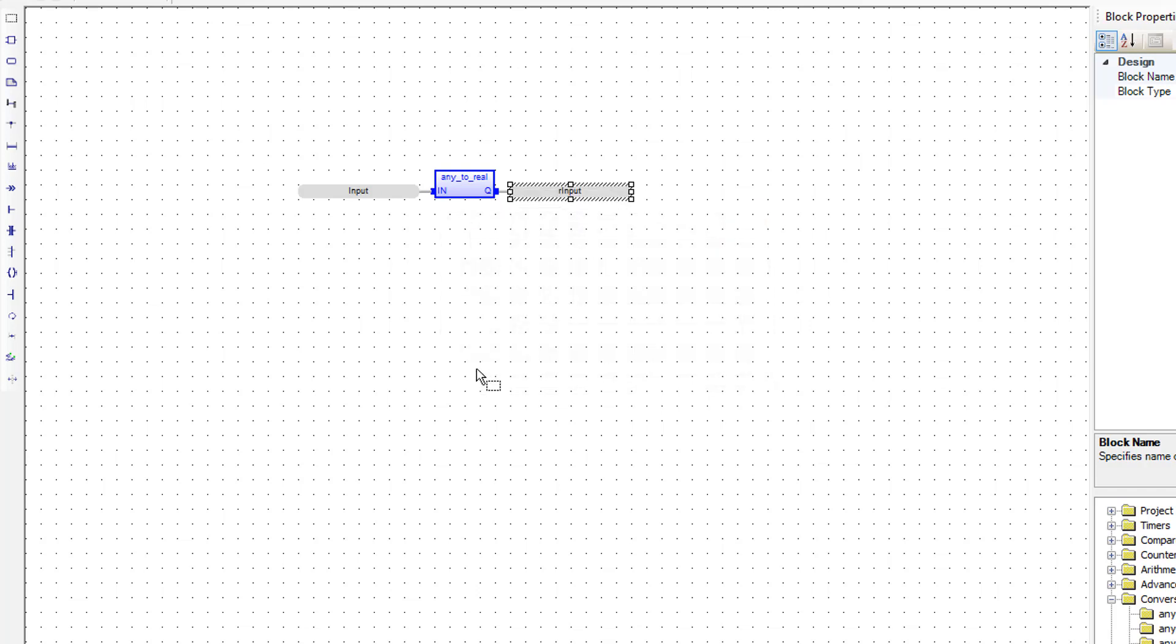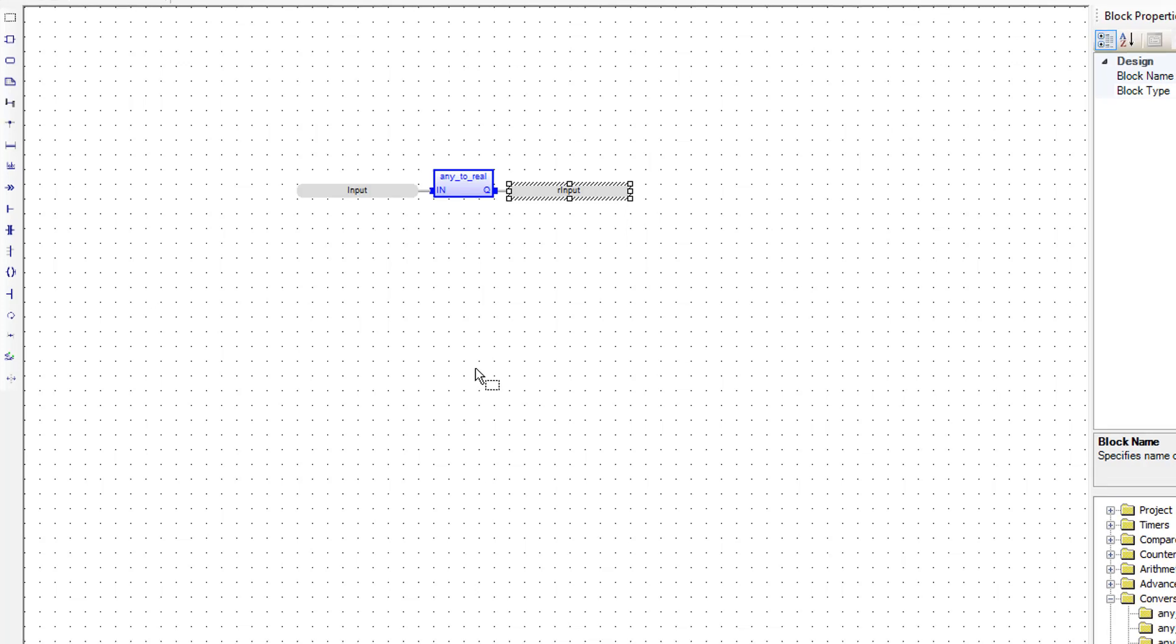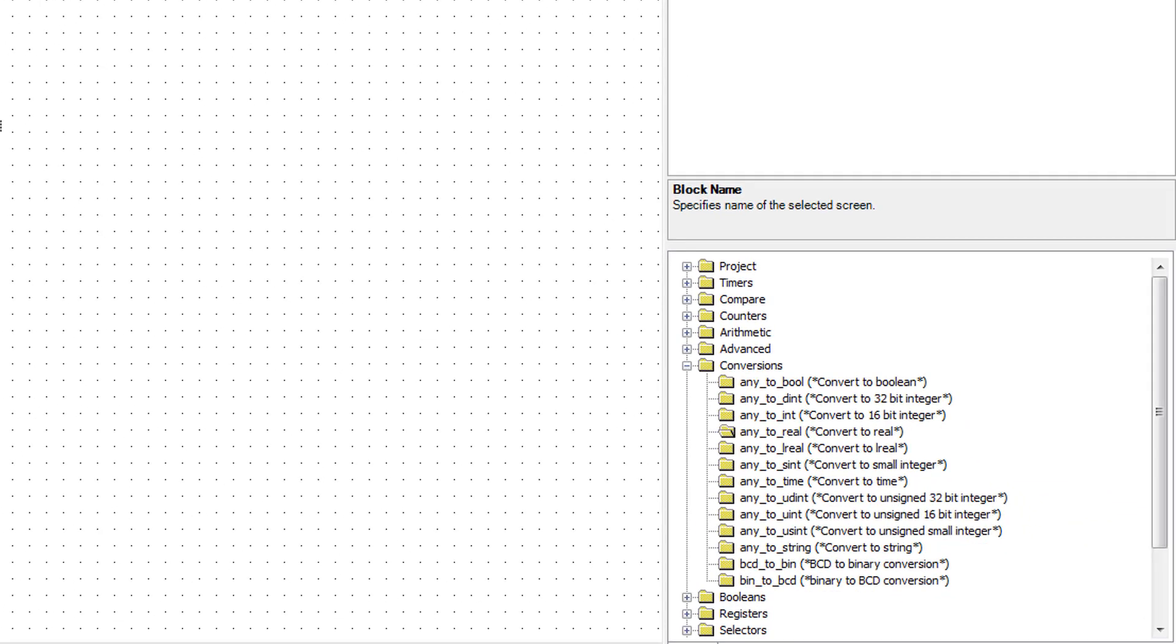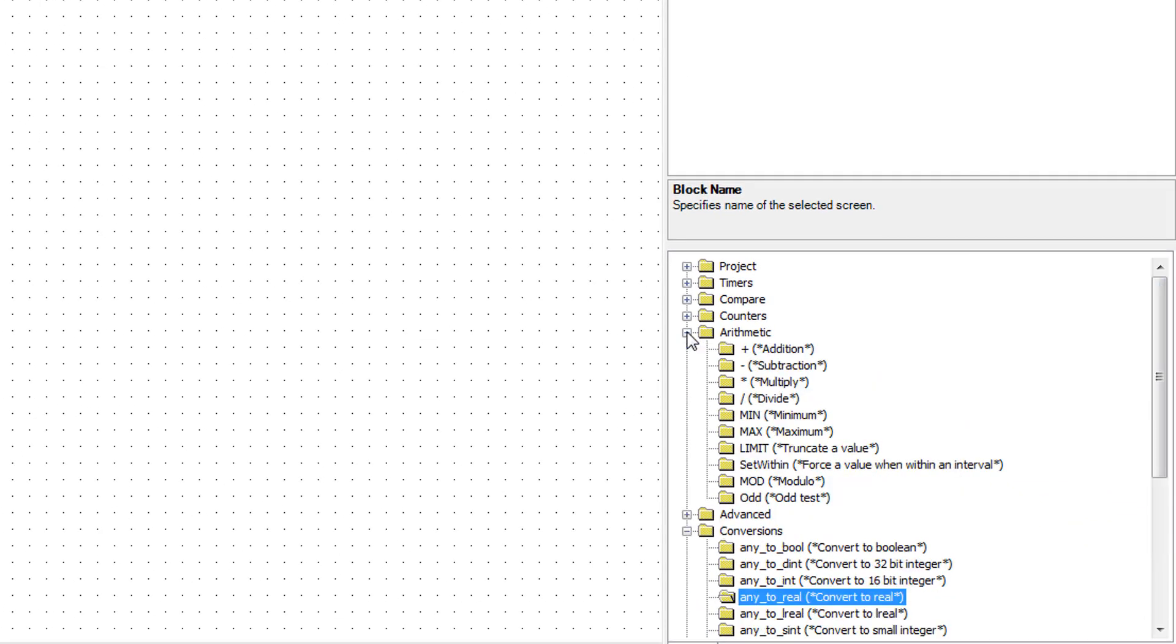So next we're going to multiply by the slope and add the offset, and that's how we're going to do our scaling. Let's go to the arithmetic section, and grab a multiply, and bring it over here.